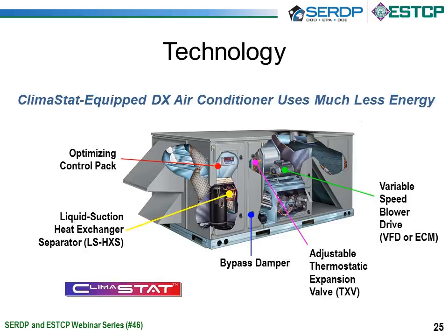So a ClimaStat equipped air conditioner has these changes made to it. These are the components that are added or changed from a basic air conditioner. We have the optimizing control pack or a standard PID temperature controller. We add the liquid suction heat exchanger separator device into the refrigerant circuit. We add a bypass damper to the evaporator coil. If the unit doesn't already have an expansion valve or an adjustable expansion valve, we either change the expansion valve or add an adjustable thermostatic expansion valve. And then finally we use either a variable speed ECM blower motor or put a variable frequency drive on the blower motor. And that's essentially what transforms a basic package air conditioner into a ClimaStat equipped air conditioner.